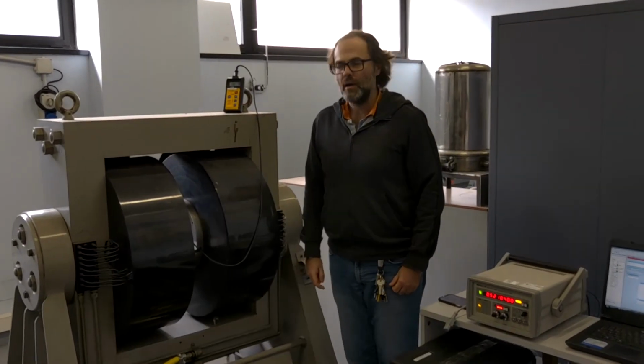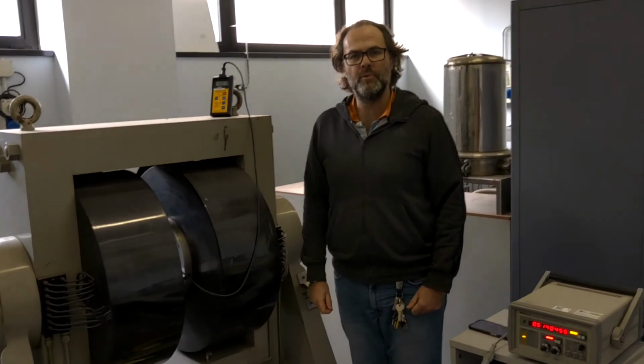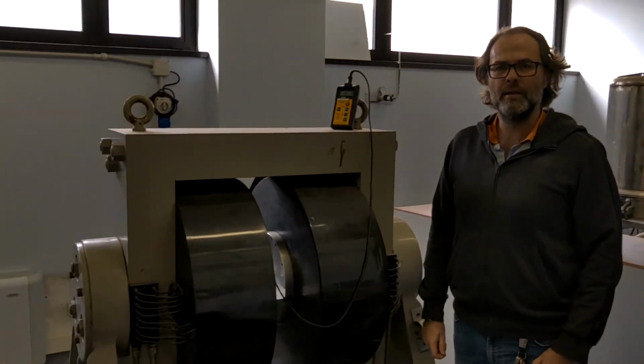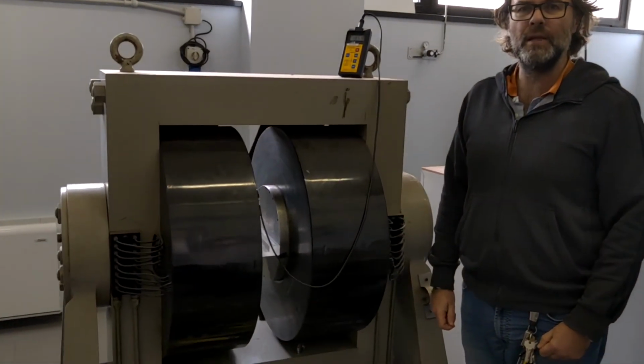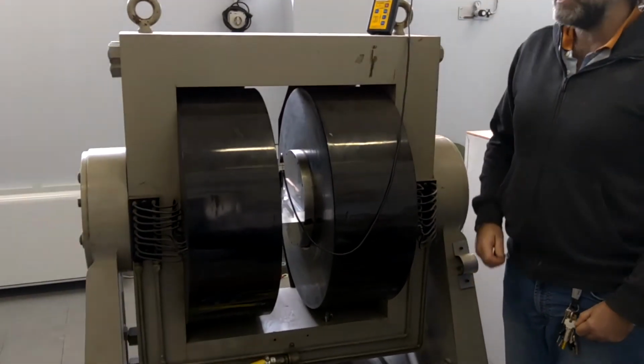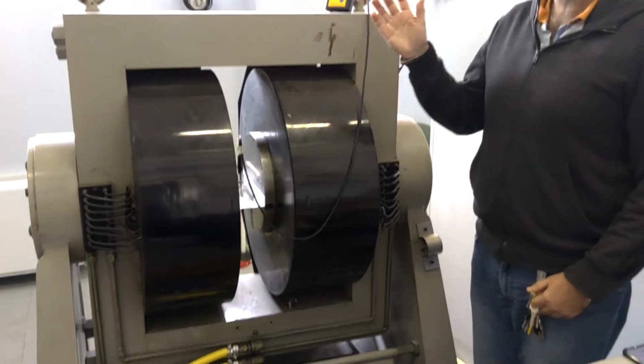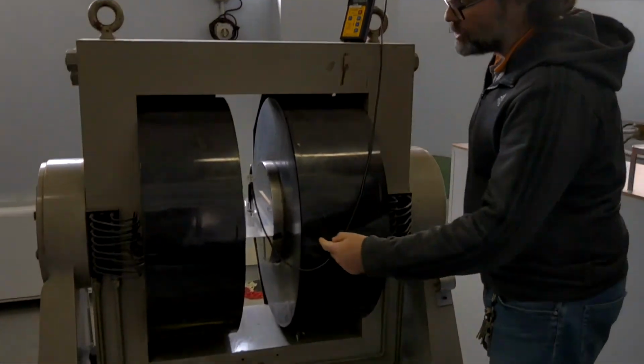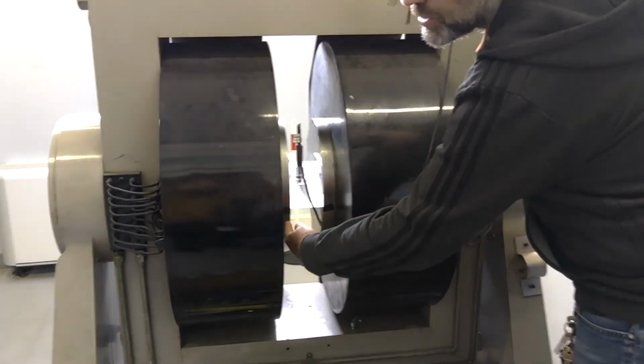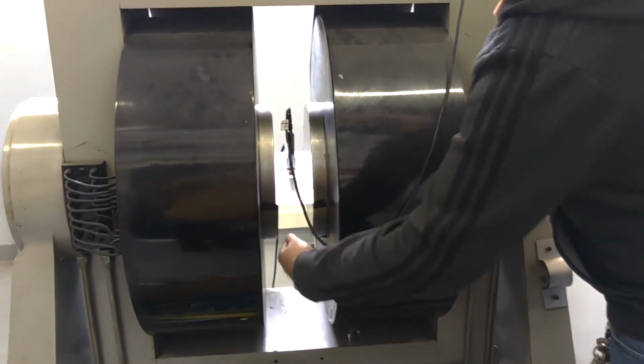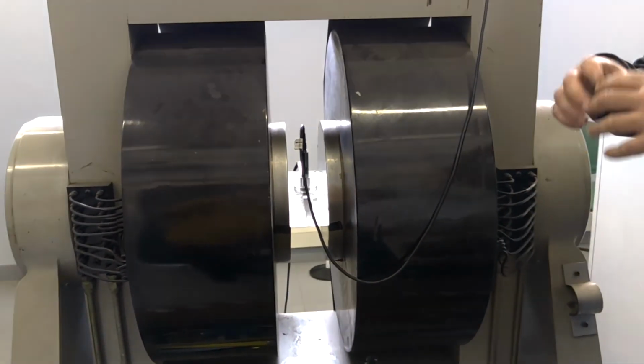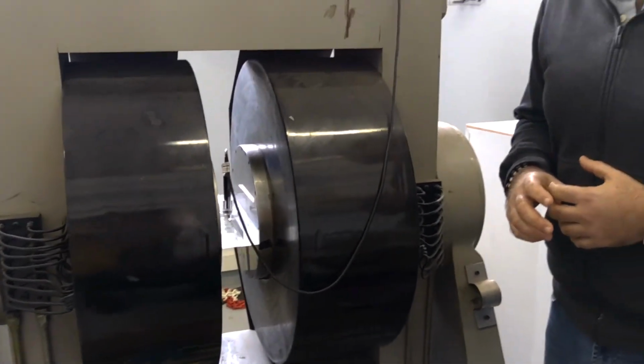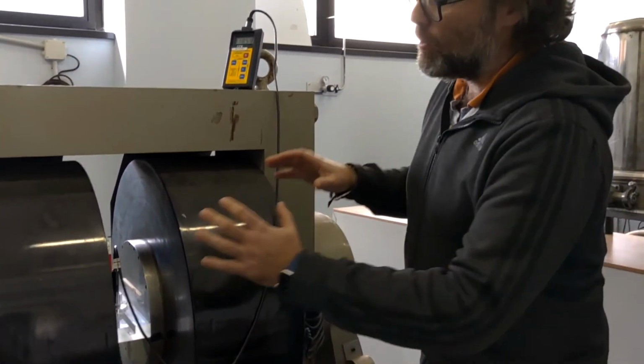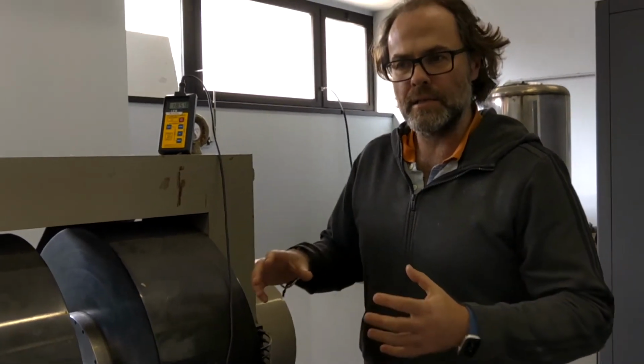With this video, I want to show you how we calibrate a magnetic probe in the field range within 50 millitesla and 1 Tesla. To do such a task, we need an electromagnet with large and flat poles, because we want to be sure that the volume in which the magnetic field is homogeneous is sufficiently large. For our magnet, the size of the volume of homogeneity is approximately 10 centimeters.